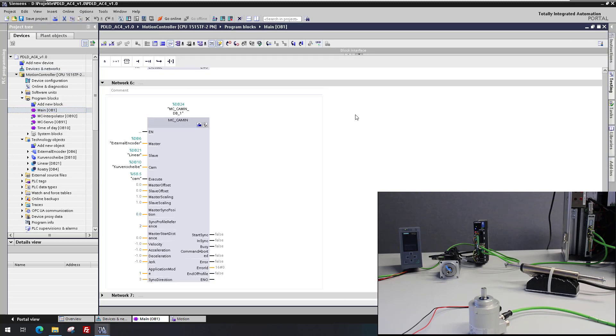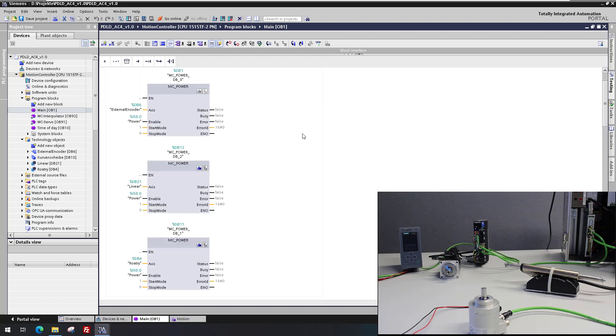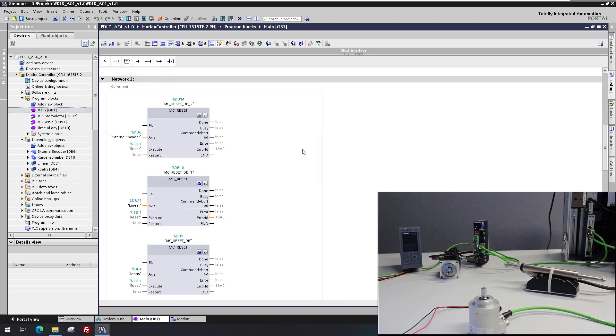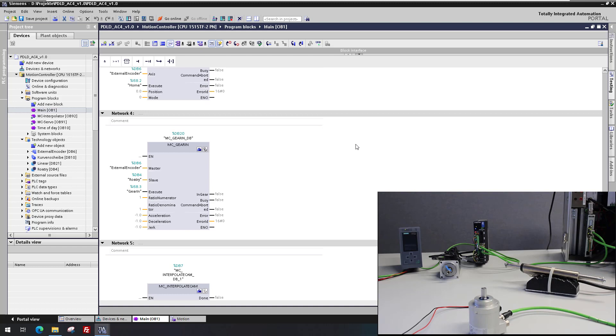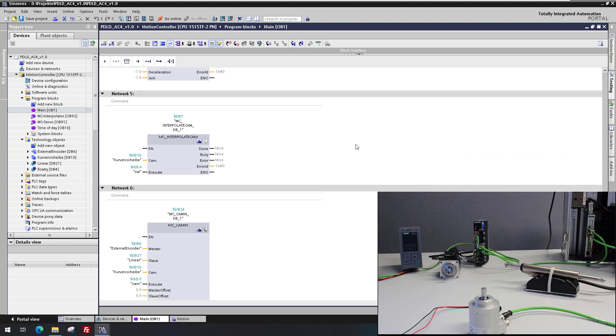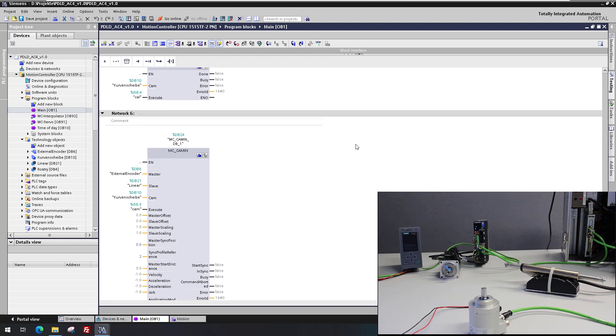The following PLC Open blocks are used inside this application: MC_Power to enable the three components; MC_Reset to acknowledge possible alarms and to restart the technology object; MC_Home to reference or set the actual position; MC_GearIn to start a gearing operation between the external encoder as leading value and the rotary axis as following axis; MC_InterpolateCam to close gaps between defined interpolation points, interconnected to MC_CamIn for synchronized movement of the linear following axis.